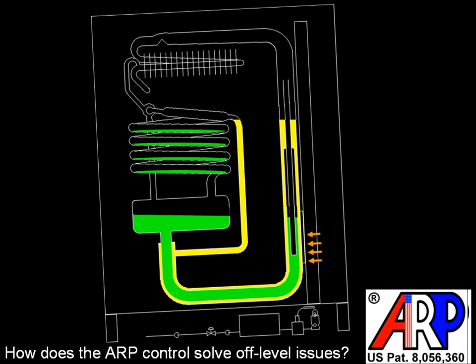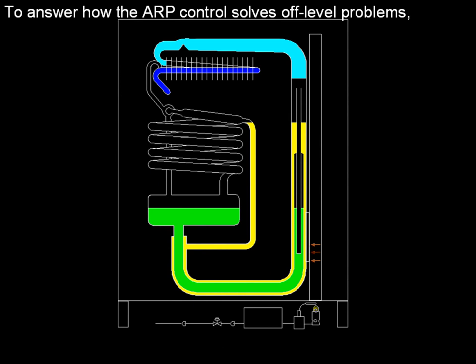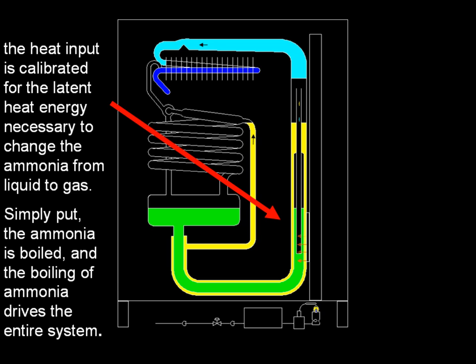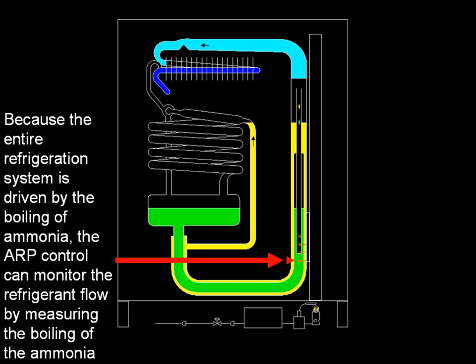How does the ARP control solve off-level issues? To answer how the ARP control solves off-level problems, the heat input is calibrated for the latent heat energy necessary to change the ammonia from liquid to gas. The ammonia is boiled and the boiling of ammonia drives the entire cycle. Because the entire refrigeration system is driven by the boiling of ammonia, the ARP control can monitor the refrigerant flow by measuring the boiling of the ammonia.